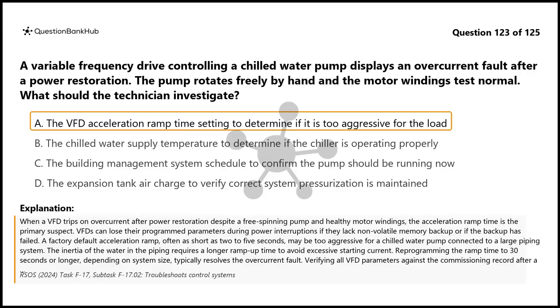chilled water pump connected to a large piping system. The inertia of the water in the piping requires a longer ramp-up time to avoid excessive starting current. Reprogramming the ramp time to 30 seconds or longer, depending on system size, typically resolves the overcurrent fault. Verifying all VFD parameters against the commissioning record after a power event is a recommended practice.